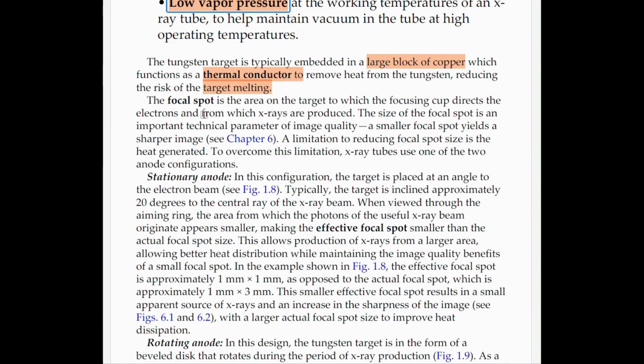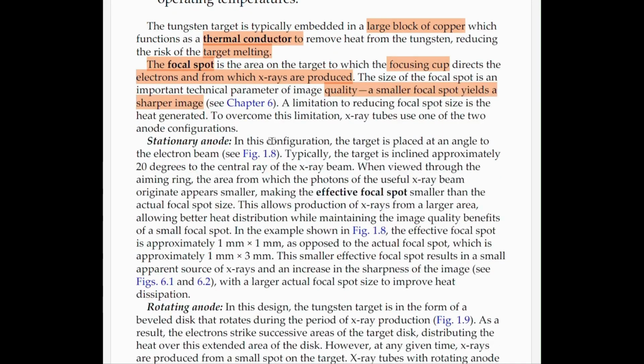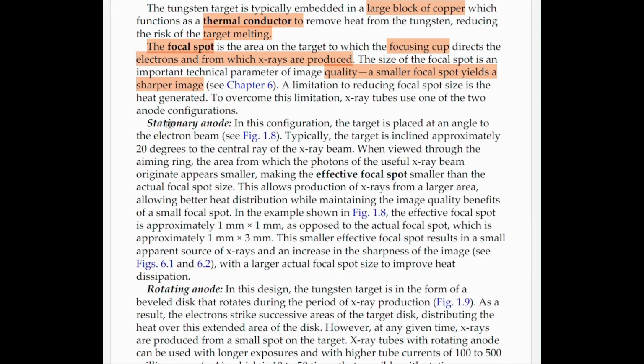Now we move on to another part of the anode, which is the focal spot. The focal spot is the area on the tungsten target to which the focusing cup of the cathode directs the electrons and from which X-rays are produced. The size of the focal spot is important. Why? Because a smaller focal spot yields a sharper image. But there is a limitation to this, because once we reduce the size of the focal spot, there is a lot of heat generation. So to overcome this, two techniques and methods can be used.